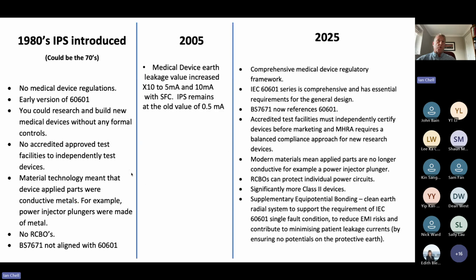So I want to walk you quickly through IPS history. In the 80s, when IPS was first introduced, you had no medical device regulations. We had an early version of 60601, and it wasn't always adhered to. And you could research and build new medical devices without any formal controls. And you could do this right up to maybe 5-6 years ago. No accredited approved test facilities to test devices.